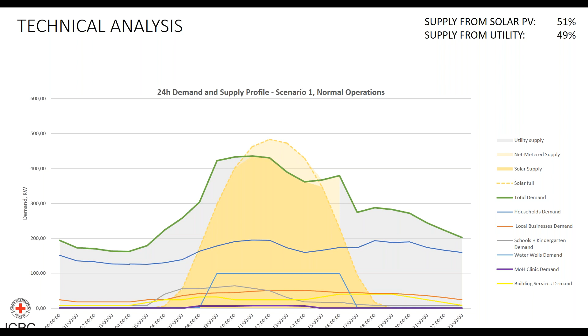During emergency operations, i.e. if the grid is off, we're considering 2 options. Firstly, with no batteries, and secondly, with batteries. It's worth noting that batteries, firstly, are quite expensive, and secondly, are often considered a dual-use item in Gaza, so it might be quite difficult to bring them in. When there are no batteries, the generators must run even during the solar hours to be able to energize the lines. If the generators are running, then they have to run at a minimum of 30% of their capacity in order not to cause damage to the generator itself. In this case, any surplus solar electricity will be lost since there is no energy storage mechanism. So you can see this is not the most efficient setup.